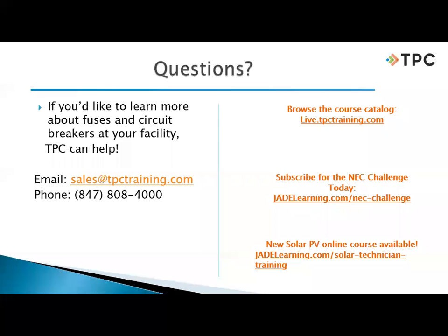The first question we have for you, Bob, is about the insulated case circuit breaker, ICCB, and the low voltage circuit breakers. Do those work also on 80% operational? I take that to mean maybe 80% load. But yeah, how would you comment on that? No, those operate on 100% of the load. Only the molded case circuit breakers, the real small ones that we would have in our house or still in our facilities, those are the ones that operate on 80% of the load. The larger circuit breakers, they can operate at 100% of the load.